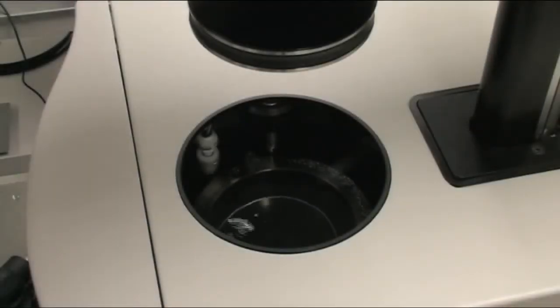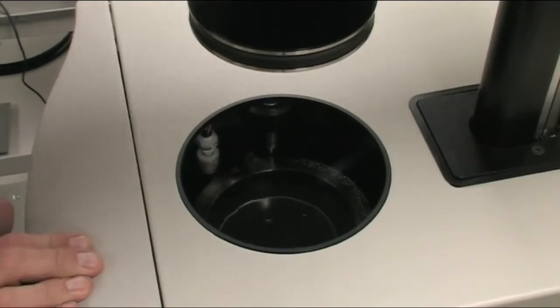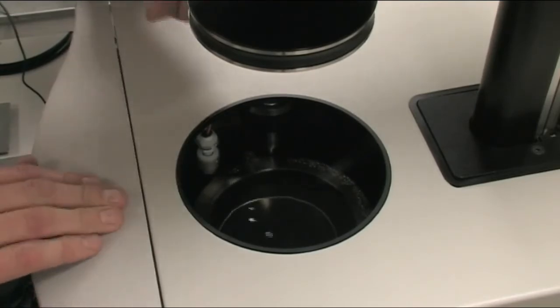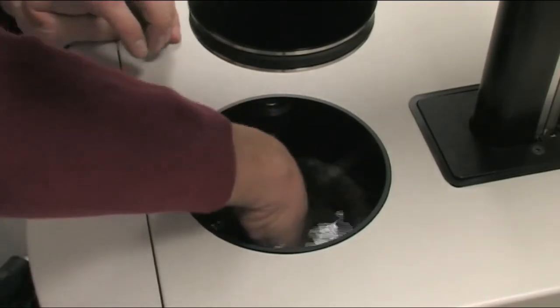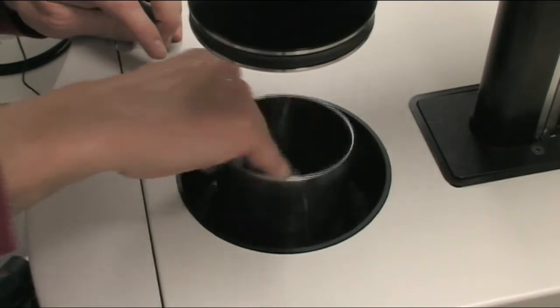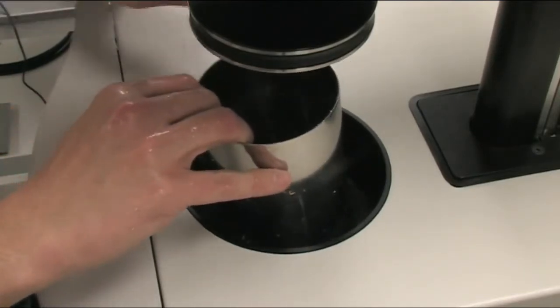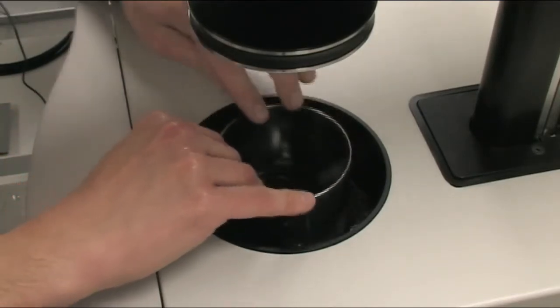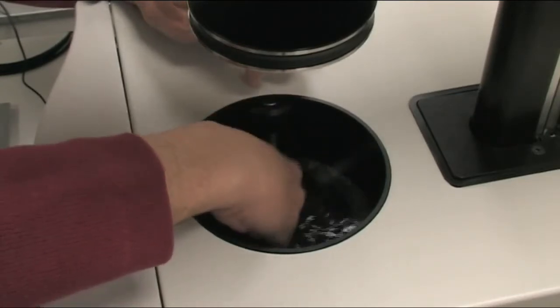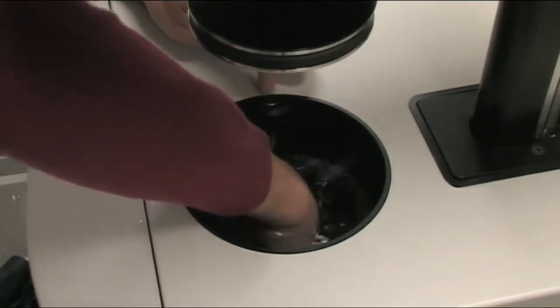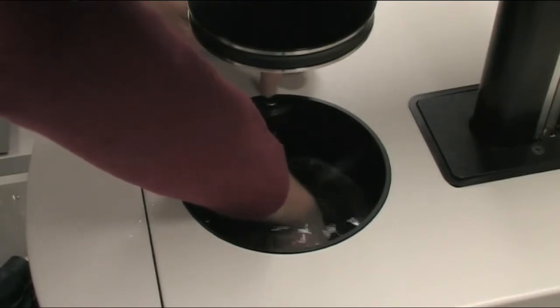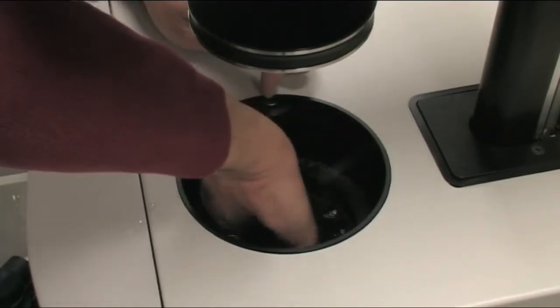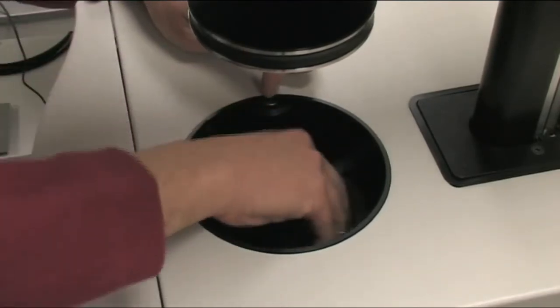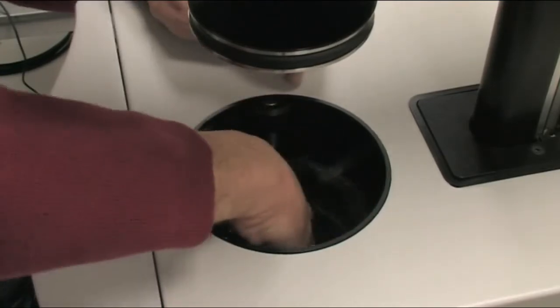One of the things you have to check after the bucket fills is to look inside and inspect for bubbles forming on the baffle and the inside of the bucket. If you do have that, you have to reach in, remove the baffle, take a soft brush and wipe all the bubbles off. What happens with the bubbles is that they interfere with the thermodynamic properties and could give you erroneous readings. Once that is completed, you put the baffle back in place.